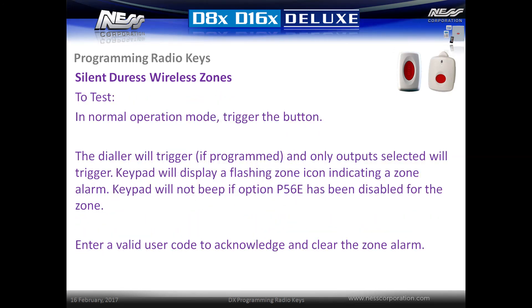To test a wireless duress zone in normal operation mode, trigger the button. The dialer will trigger if programmed, and only the selected outputs will activate. The keypad will display a flashing zone icon indicating a zone alarm; the keypad will not beep if option p56e has been disabled for the zone. Enter a user code to acknowledge the alarm and clear the notification.